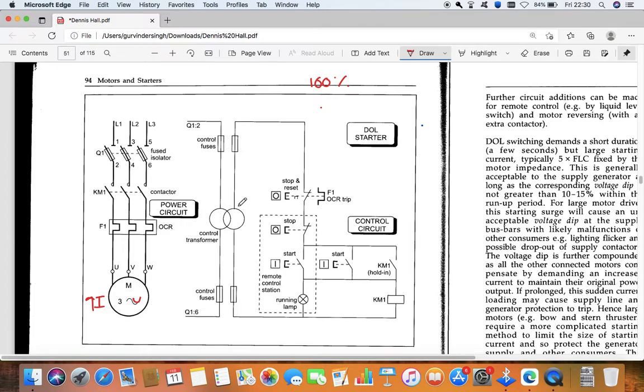What will happen if it is drawing more current? We know that heat is equal to I square R, so the heat produced in the motor depends upon the square of the current. If the current increases, the heat produced by the motor increases, it comes under losses, and it will also damage the insulation of the motor. That's why we try to reduce the starting current, and we can do that by applying a reduced voltage to the motor. When we apply a reduced voltage, it causes less starting current and less heat produced inside the motor.